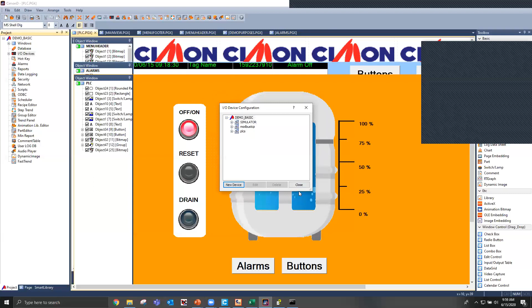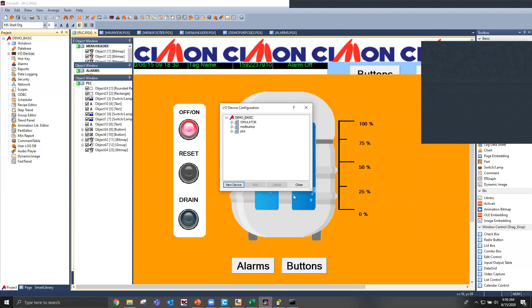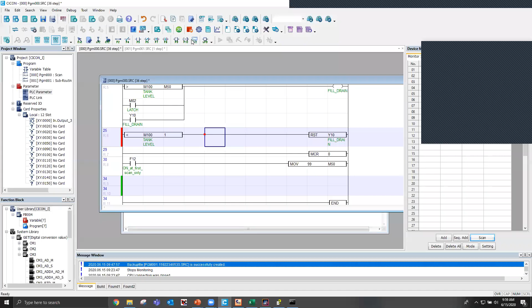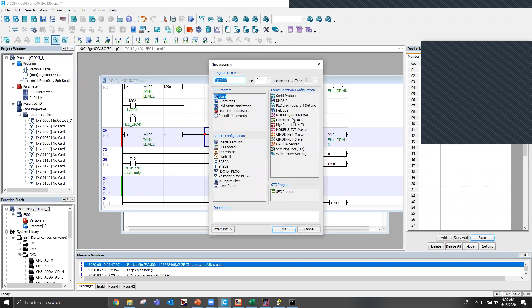I press save, close. So currently, the SCADA software is bridging communication between the PLCs and the sensor device, or you can have it just talk through Modbus through the PLC to the actual sensor device. The way to do that would be to come to the Cimon software, new program, Modbus TCP master, press OK, and you'll get a program like this. So where is the slot? And to remind you guys, you can't use the PLC's CPU as a Modbus master. So you would have to get a dedicated Ethernet module.